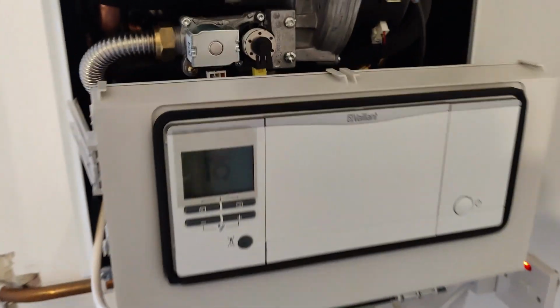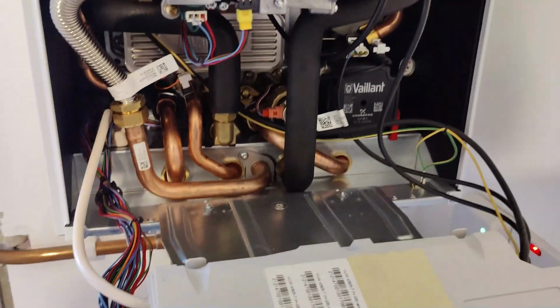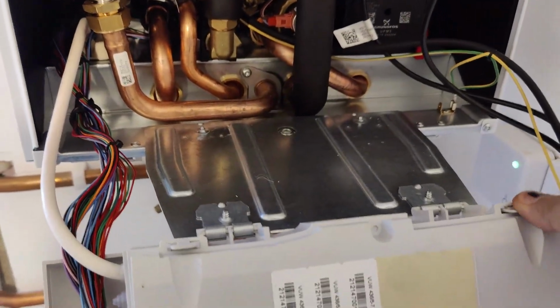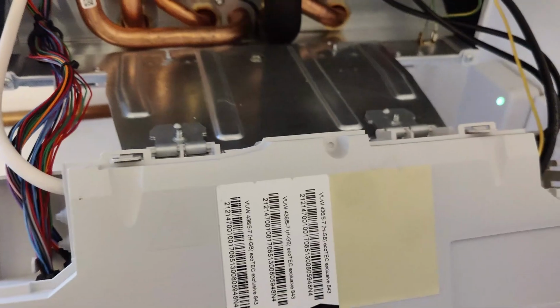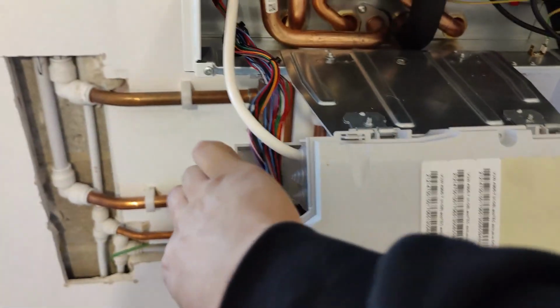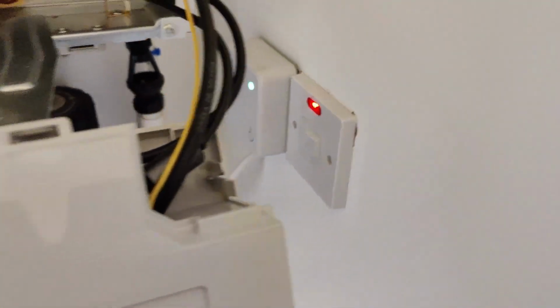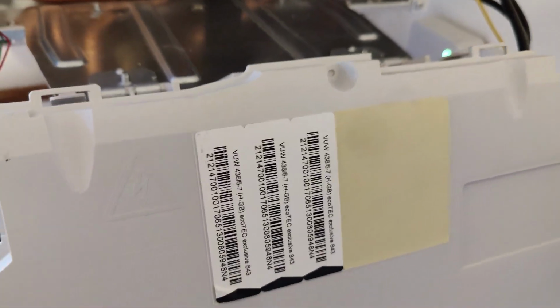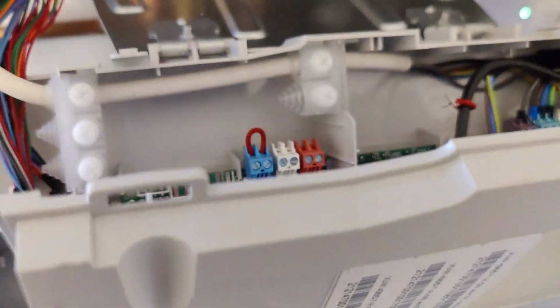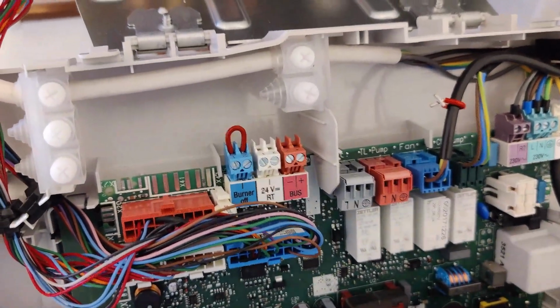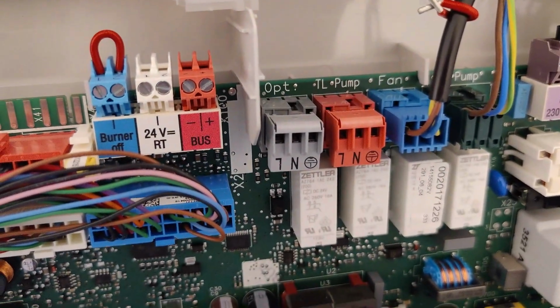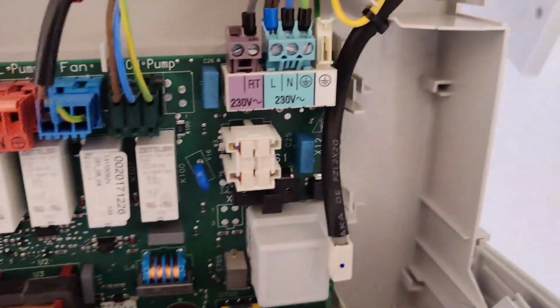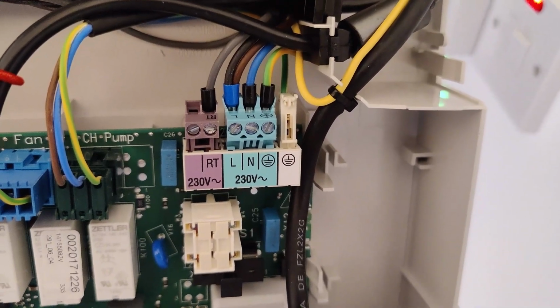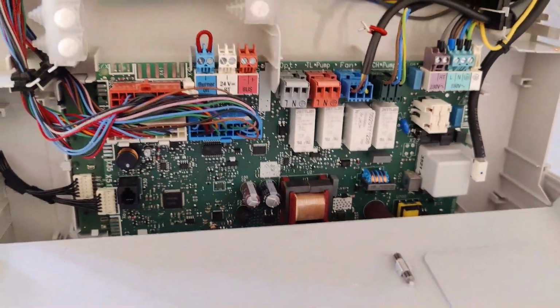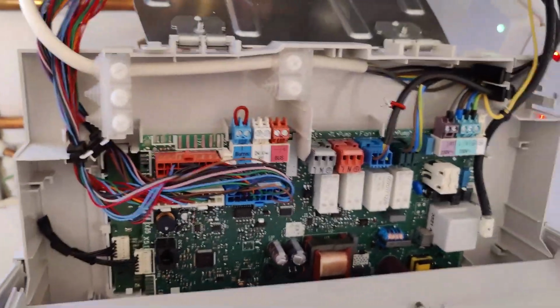Okay, so let's have a look at how we wired it about 3 years ago. Well, 2 years ago, 2022 is when we installed this boiler. Let's see if we removed or left the 24 volt contact. It's got Hive connected to it, as you can see the base there. Let's have a quick look. Oh yeah, so as you can see, the 24 volt contact loop was removed and it's wired through the RT connection. So that's the PCB for this particular beast.